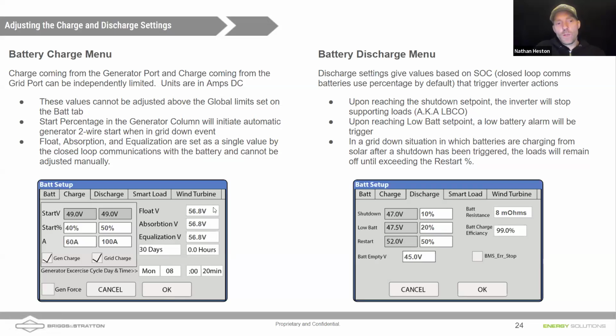Now, also note that we have the same values for float, absorb, and equalization here. With communicating batteries, the battery is going to control those settings, and it does it by setting just one common voltage that it wants to see from the charge controller. So these are smart batteries. They're going to control that automatically. Generally speaking, we would float our batteries at 54 volts. We would absorb up to 56 volts. And then we don't use an equalize function with LFP batteries. That's a lead acid battery thing. Equalize is there to have a high voltage to burn that sulfur off of the lead acid plates.